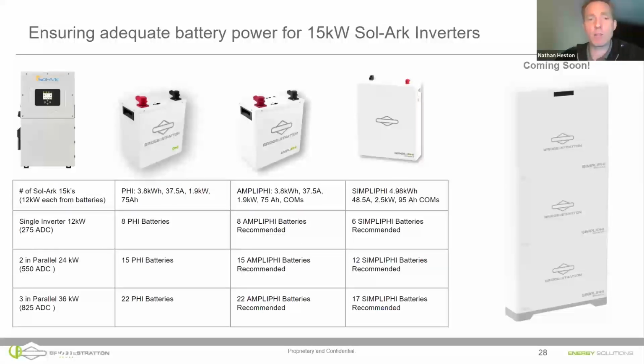So with our Phi batteries, which are non-communicating indoor batteries, we recommend that you have a minimum of 8 of these batteries for a single Sol-Ark 15K. That's to cover 12 kilowatts of loads. Now, you can go lower, but you need to make sure that you program appropriately. So at full capacity, 15 batteries would cover 2 paralleled Sol-Arks, and 22 batteries would be enough to do 3 paralleled Sol-Arks, 36K of continuous output on 825 amps DC. On the SimpliPhi batteries, they have closed loop communications. You can do less than the recommended number of batteries. You'll get a shorter runtime. However, you will also get less total power output than that 12 kilowatts from batteries that the inverter will deliver. And that will happen automatically.